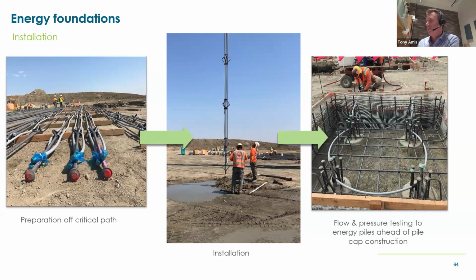But the foundation world has a solution for dealing with these kind of ground conditions called a displacement pile. The Malcolm guys were phenomenal, achieving over 30 piles per day per rig down to about 120 feet - that's about 3,200 feet a day of geothermal loop. One drilling rig drilling a purpose-drilled borehole would take 1 day to drill 500 feet and put a loop in. So you can see the immediate benefits of an energy foundation solution on this project, not only from the lack of contamination that needed to be carted off site, but also the speed at which work was done - there was no impact on the construction schedule.